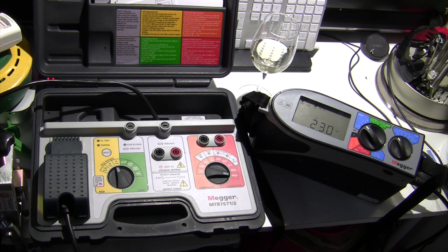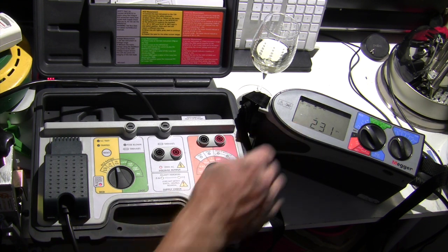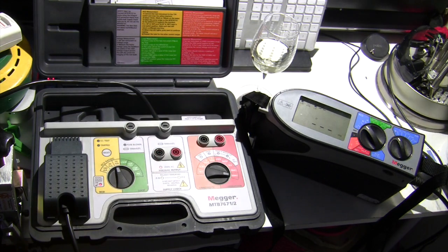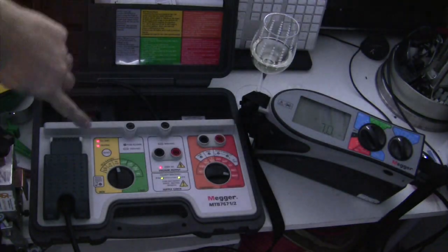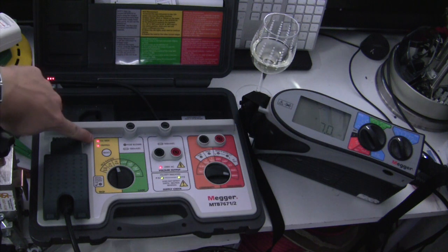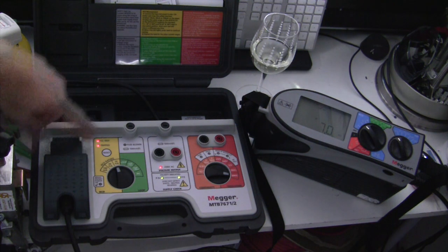Again, it'd be 40 milliseconds in real life would be your upper limit. It's 10 milliseconds for the check tester here. So we're at 0 degrees again, 5 times rated current. Off we go. We want to see a result below 10, and indeed we get a result below 10. We get 7. I'm just going to turn the light off one more time because we're slightly different now. Not only have we got the tripped light on, but we've got a second light which says it's tripped at 5 times rated current.